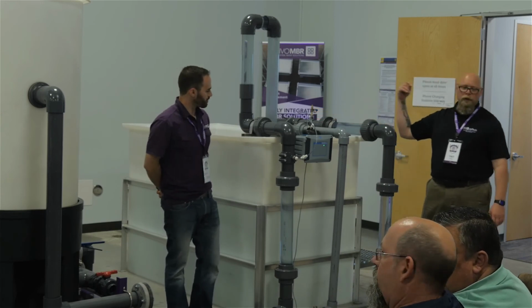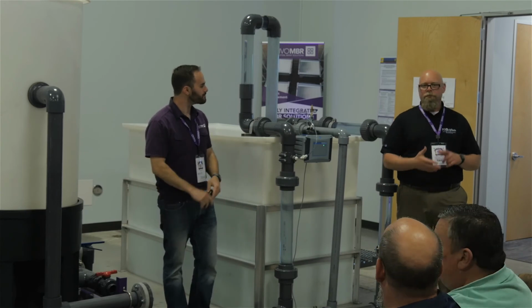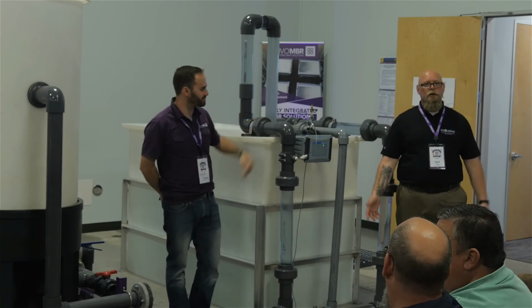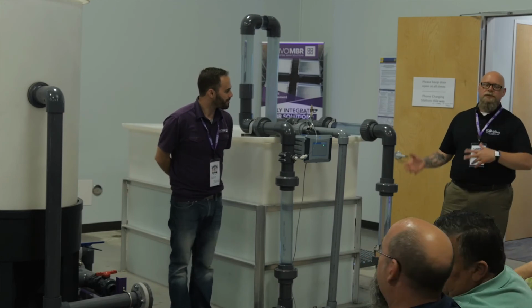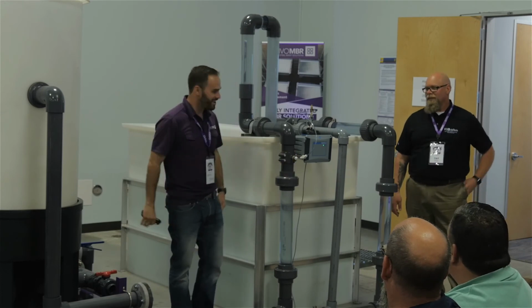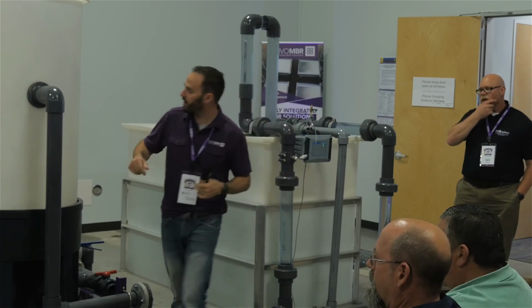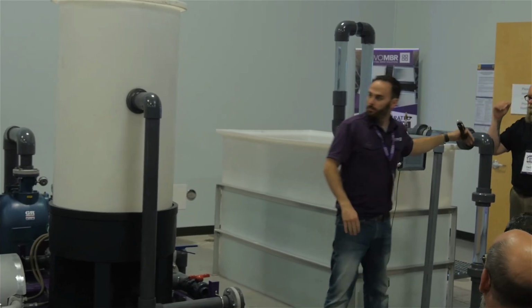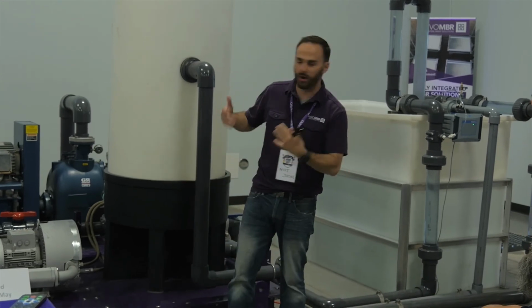We can simulate some type of leak or way for air to get into your permeate suction system. Yeah. We are simulating a hole. That's what we're doing. And we're using a hole to do it. But, so, anyway, what we've got going here is the system is stable. Like I said, the pipe is totally full of water. But what we're going to do is introduce air into this system and show you the before and after effects of what happens when you have air in the system.